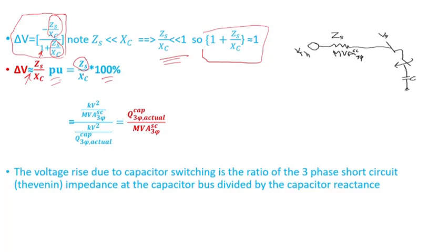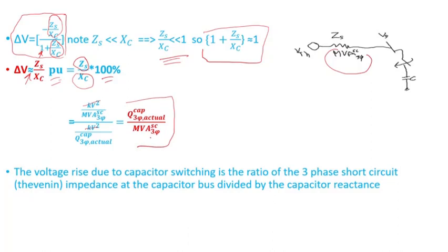ZS, the Thevenin impedance of the system, equals the system voltage squared divided by the available short circuit MVA. XC equals the system voltage squared divided by the actual reactive power rating of the capacitor bank. Since the voltage terms are the same they cancel out, and we end up with the actual rating of the capacitor bank divided by the available short circuit MVA of the system.